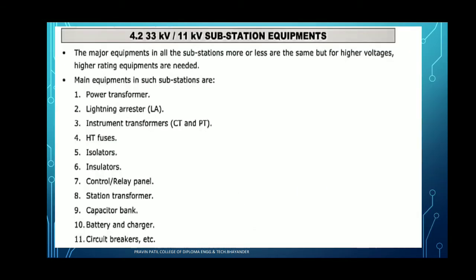Next, 33 by 11 kV substation equipment. Which are the main equipment required in a 33 by 11 kV substation? The main equipment are listed as given below: power transformer, lightning arrestor, instrument transformer, HT fuses, isolator, insulator, control relay panel, substation transformer, capacitor bank, battery and battery charger, circuit breaker. So these are the components which are required for a 33 by 11 kV substation.